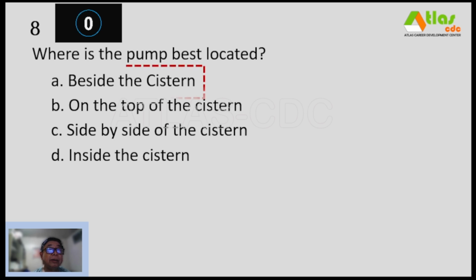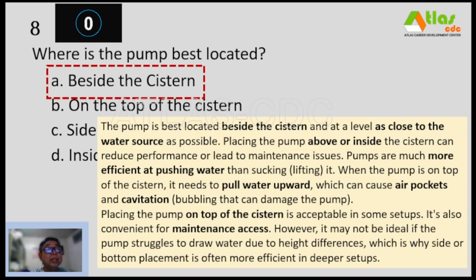And our correct answer is letter A, beside the cistern. So the pump is best located beside the cistern and at a level as close to the water source as possible. Placing the pump above or inside the cistern can reduce performance or lead to maintenance issues. Pumps are much more efficient at pushing water than sucking or lifting it. When the pump is on the top of the cistern, it needs to pull water upward, which can cause air pockets and cavitation or bubbling that can damage the pump.